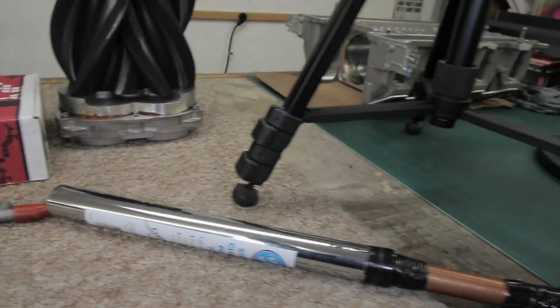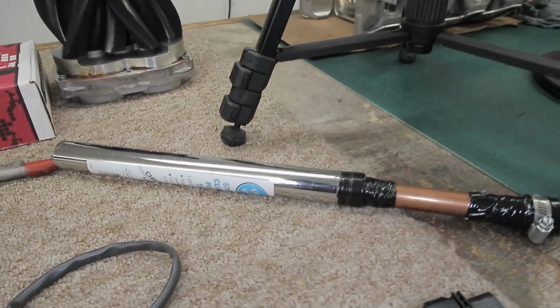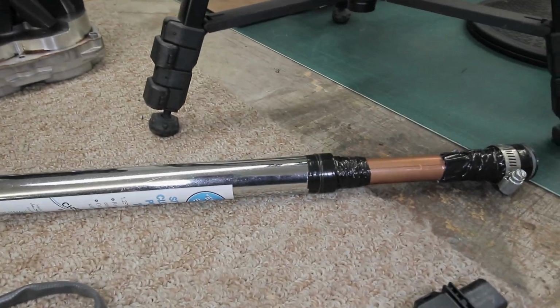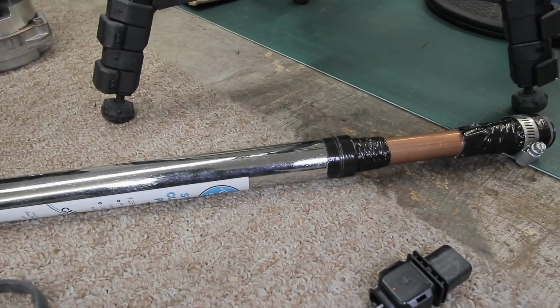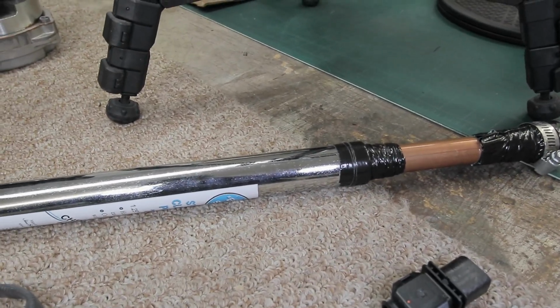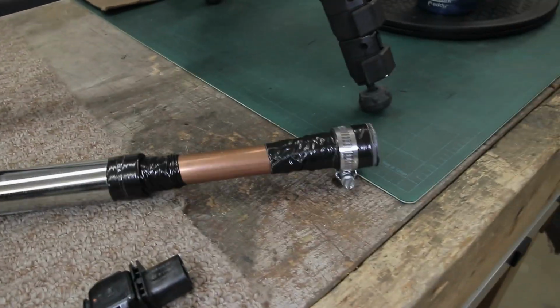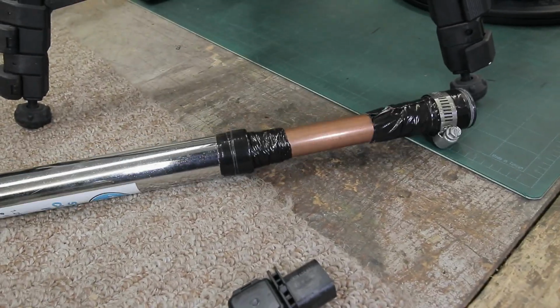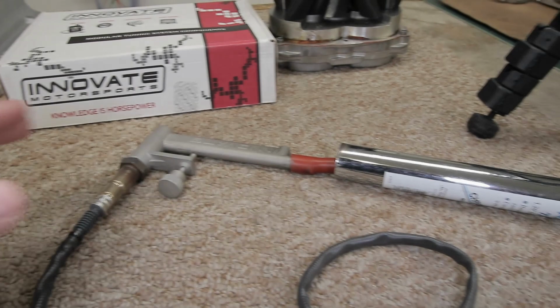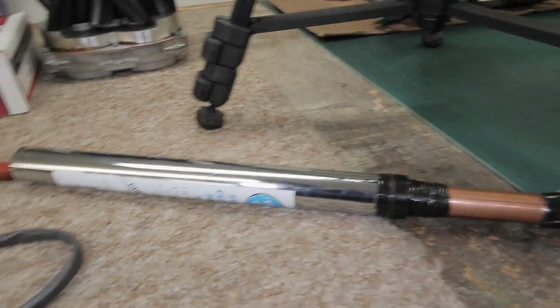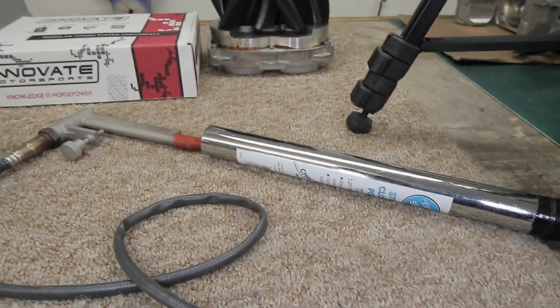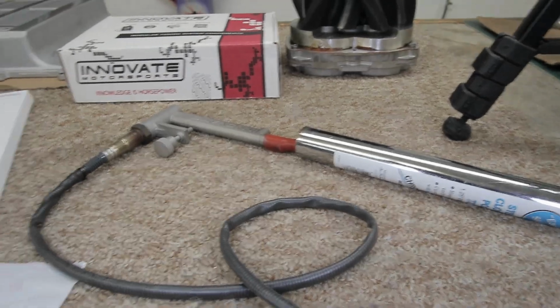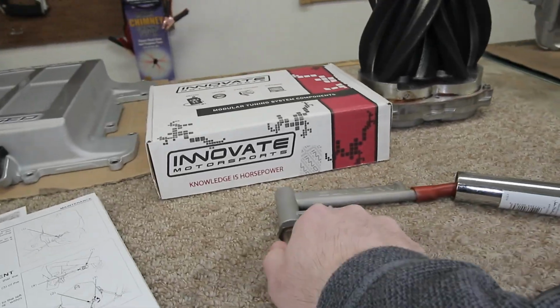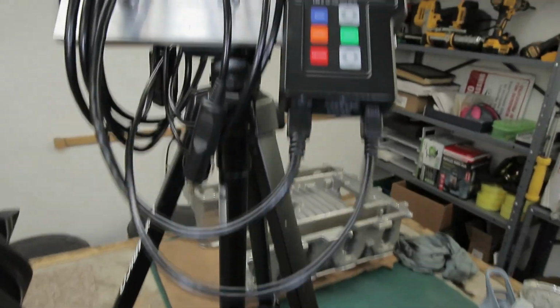This works properly. I've already tried it on the machine so I know it's going to work, but I couldn't get a good, stable reading without doing all this mounting and adapting to the sensor. You have to have the sensor buried deep inside the exhaust stream to get a reliable reading. So that works out good, and this plugs into the meter.